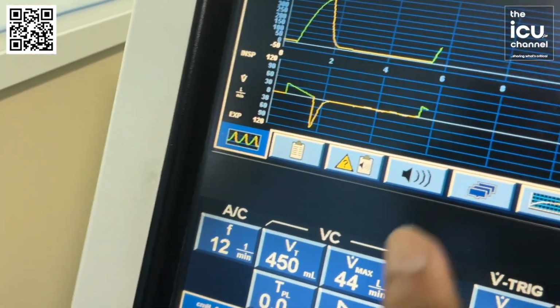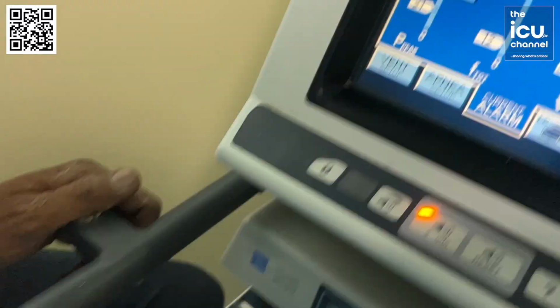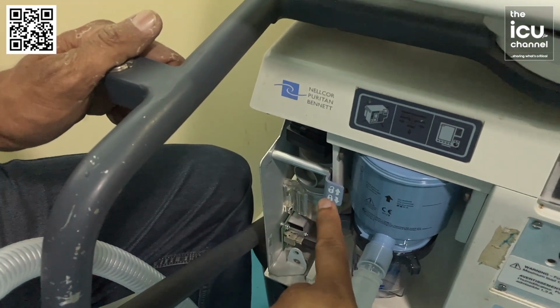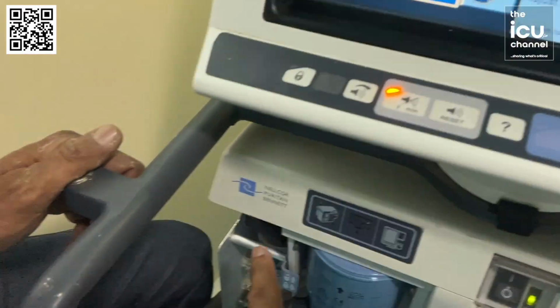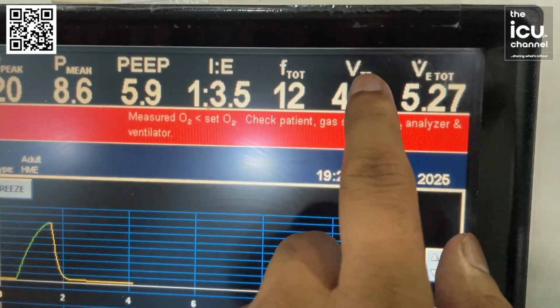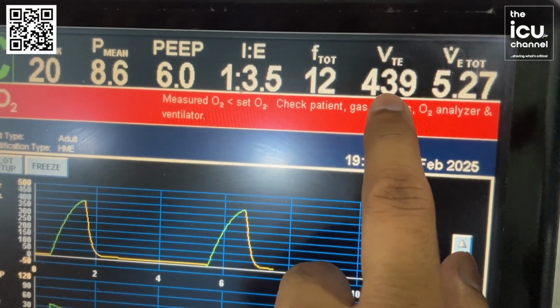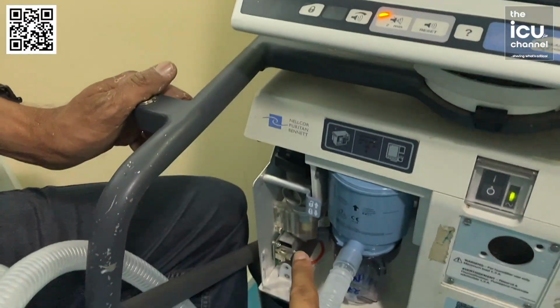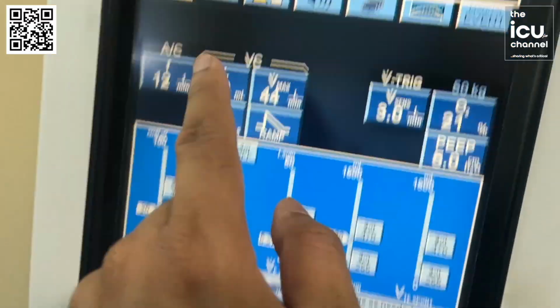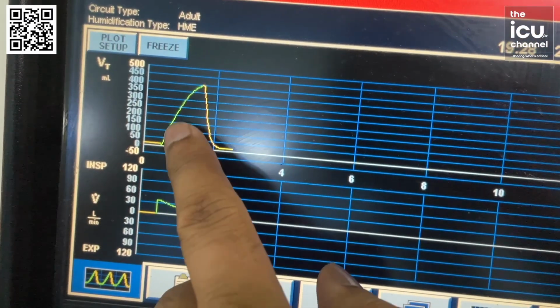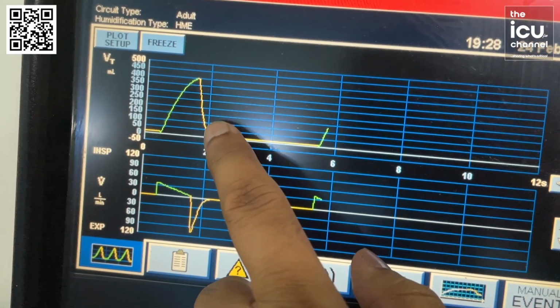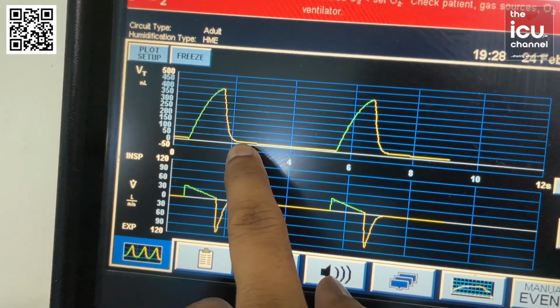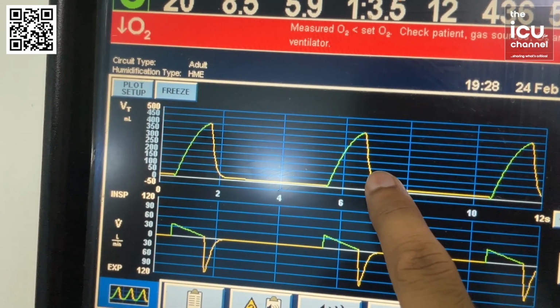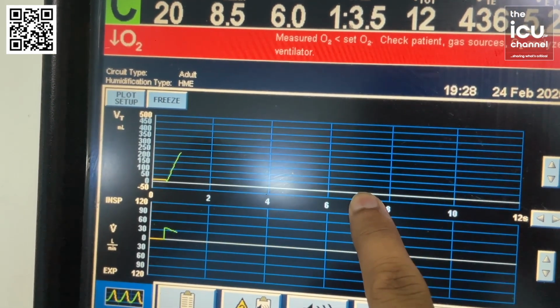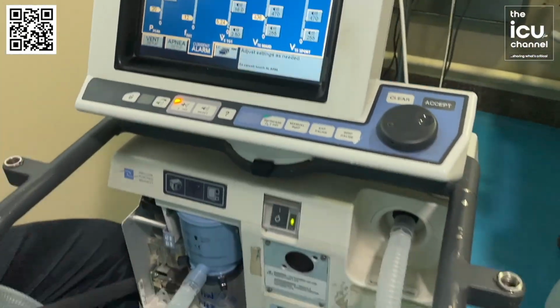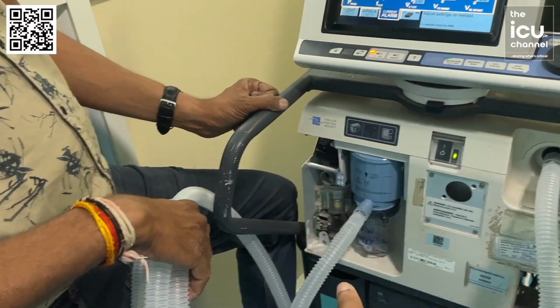Now, where is the expiratory tidal volume? This expiratory flow sensor and the expiratory leak valve are sensing, and the value which is getting shown is here. You see tidal volume exhalation, expiratory. So this is the amount of tidal volume which is being returned to the circuit, and it is sensed by the expiratory flow valve. So suppose this inspiratory limb is delivering 450 tidal volume, but if something is leaked there, this will very steeply fall. There will be a vertical line, and it will tell that there is a leak in the circuit. Now, leak in the circuit can be from here in the circuit to there.